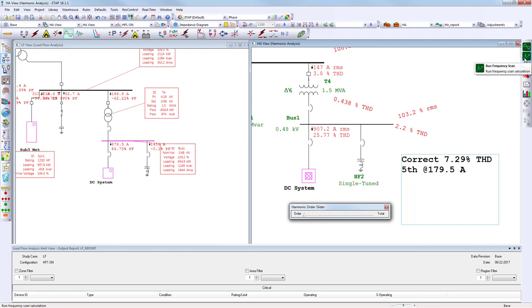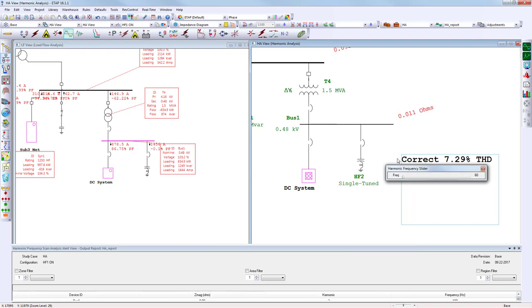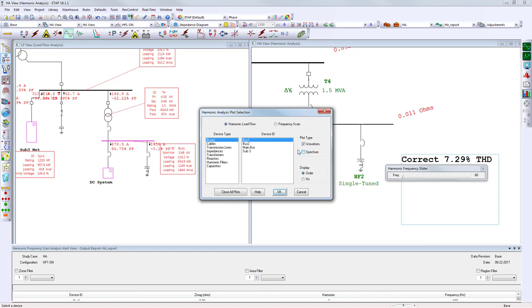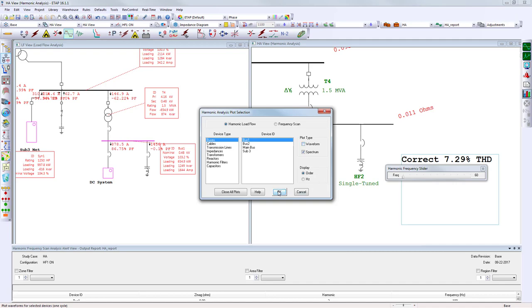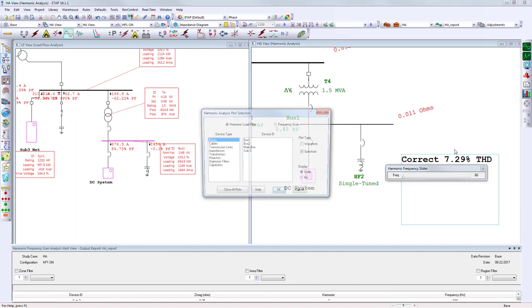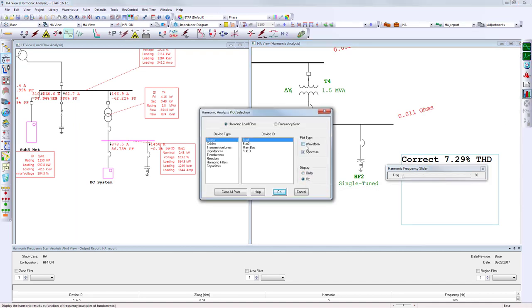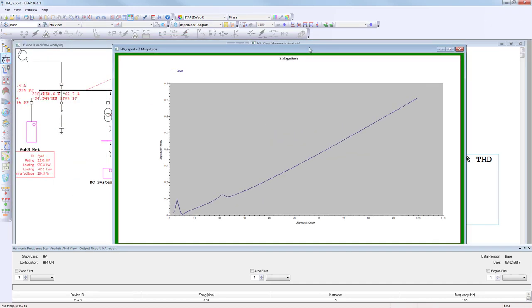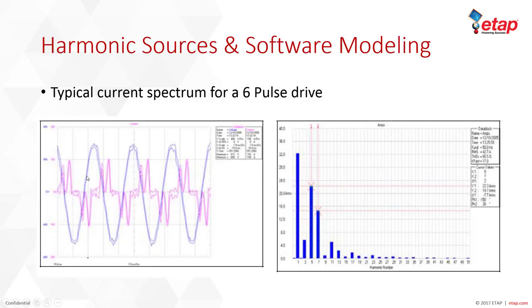The last piece of information to cover is running a frequency scan. Select 'Run Frequency Scan', open the plots, and look at the waveform and spectrum for bus number 1. The frequency scan shows harmonic order on the x-axis versus impedance, making it easy to identify the various resonances and better tune the filter. Thank you for watching this presentation.